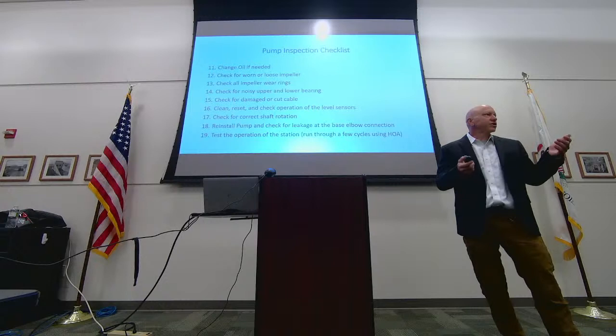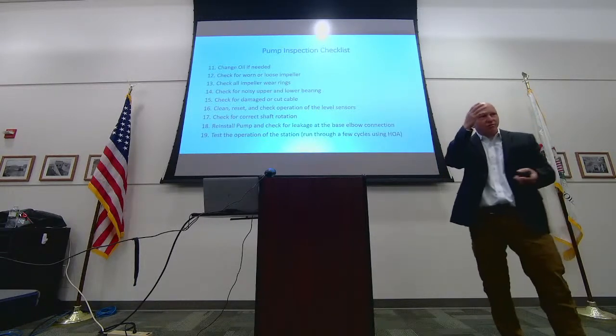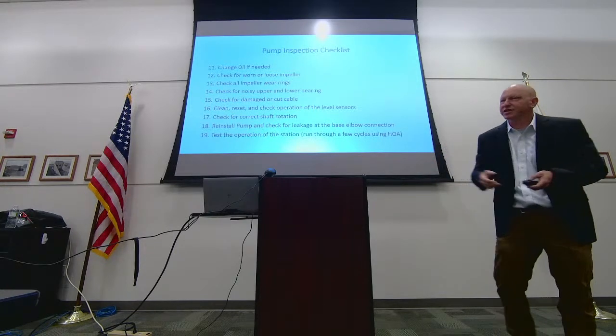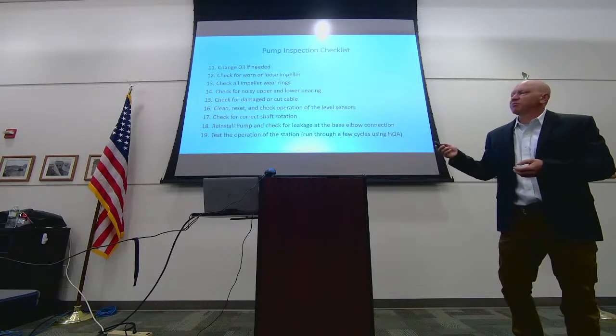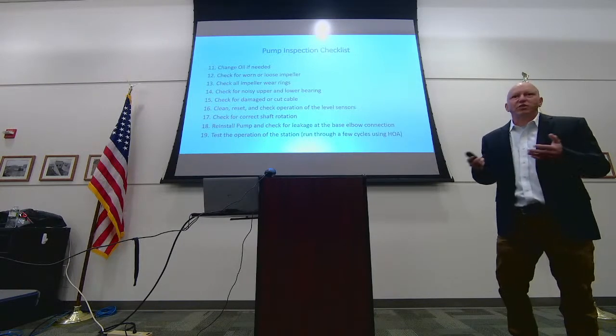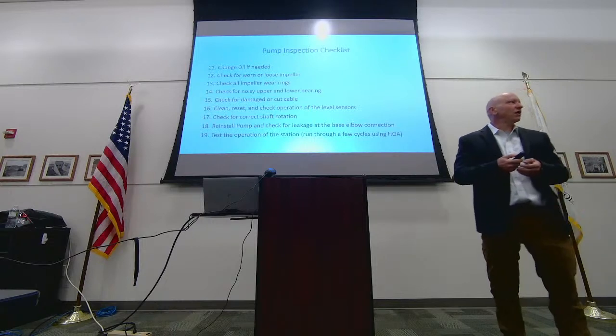When I do a service agreement for you, we give you a report. Hey, this is what your equipment looks like. You're at 80% life or you're at 60% life. A worn or a damaged impeller is the easiest thing to see, the least expensive fix 9 times out of 10 to get you back to where you want to be operationally.